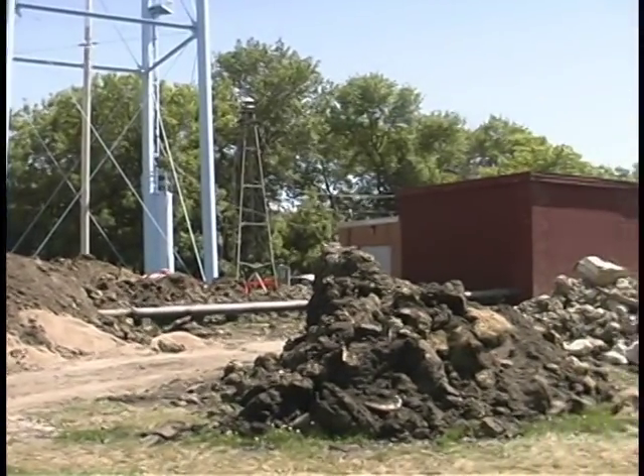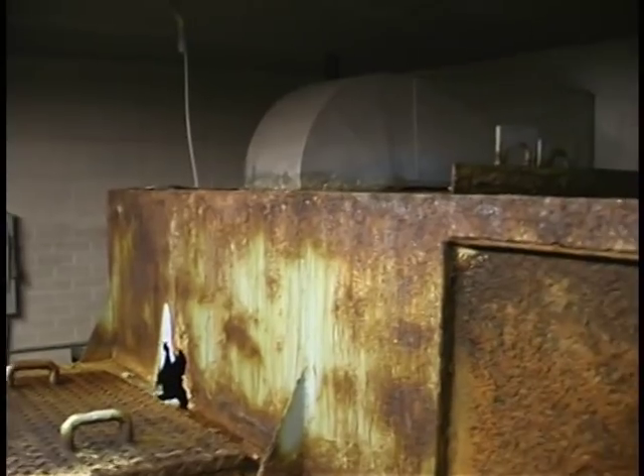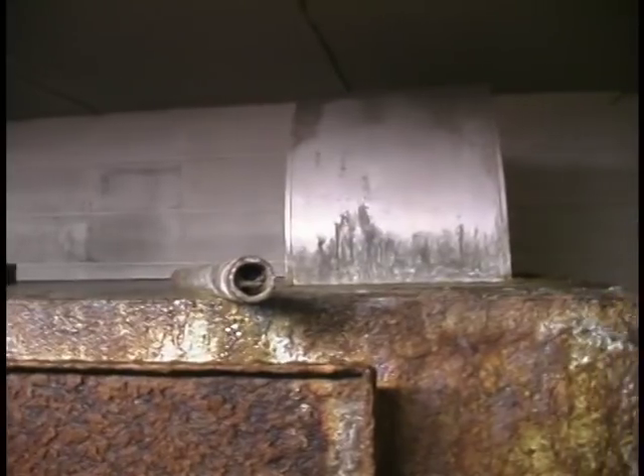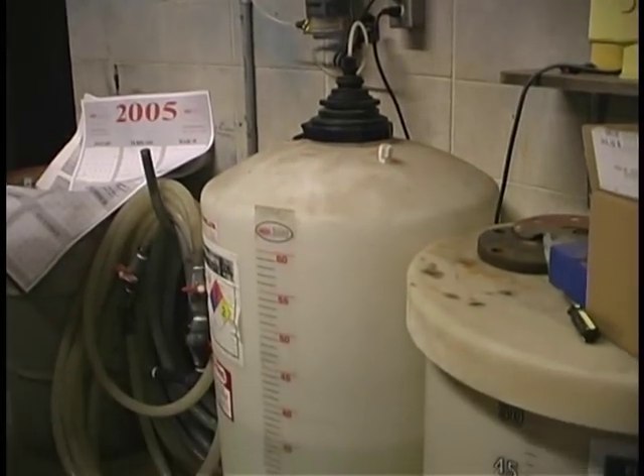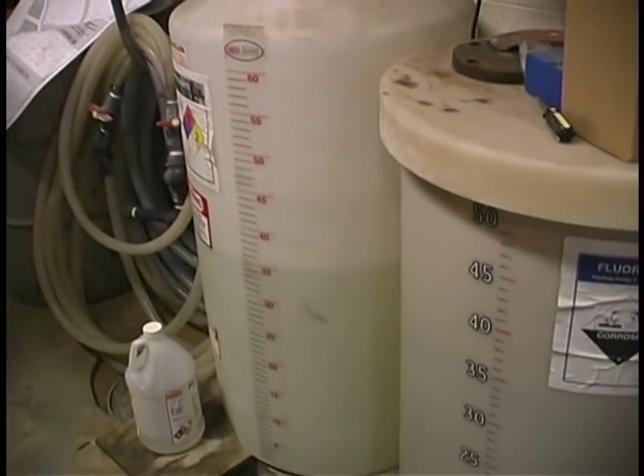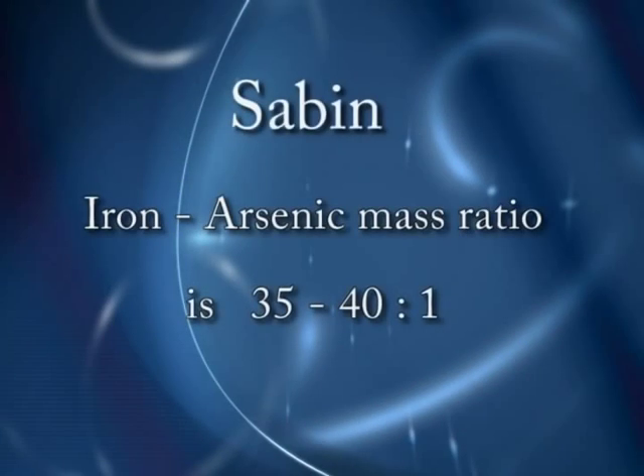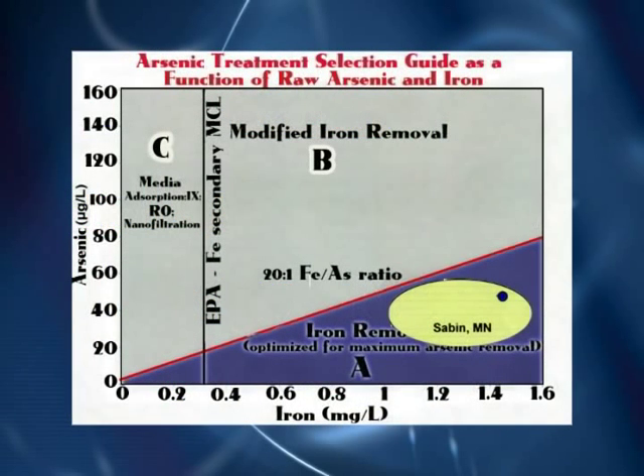The raw water arsenic concentration was below the old arsenic MCL but above the revised MCL of 10 micrograms per liter. The existing plant consisted of aeration to oxidize iron (though that part was not functional), gravity filtration through a sand filter, fluoridation, and chlorination. The raw water has sufficient iron to provide a 35-to-40-to-1 iron-to-arsenic ratio, placing the system in zone A and making it an ideal candidate to use the naturally occurring iron for arsenic removal.